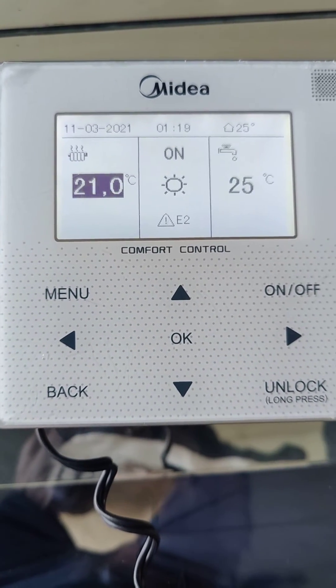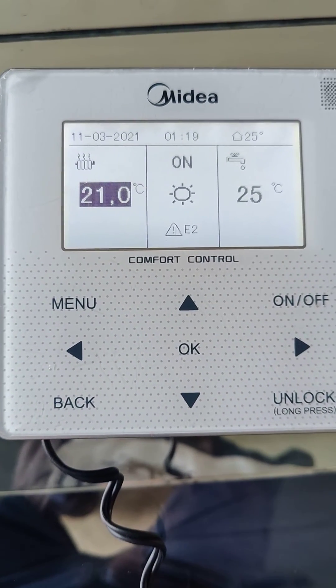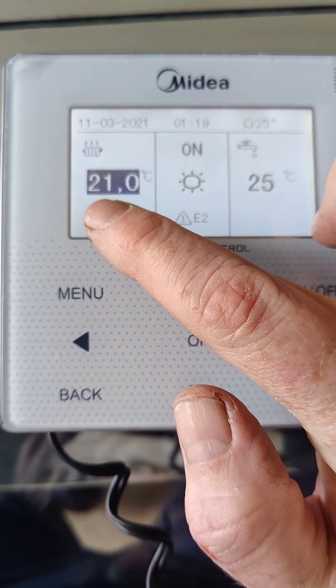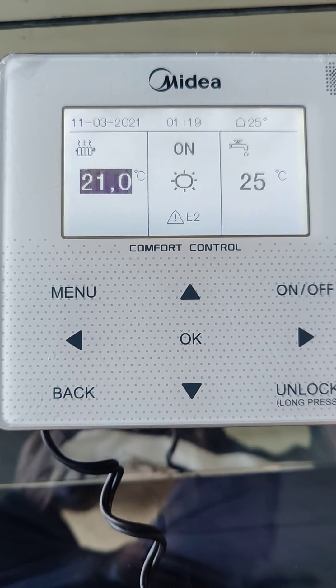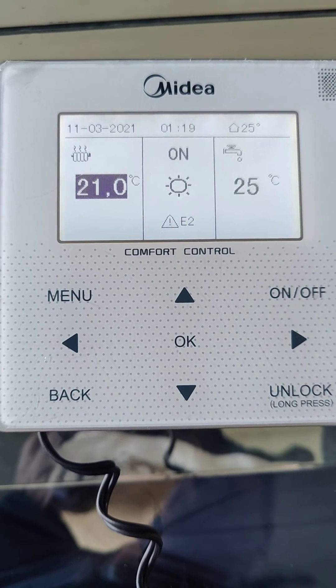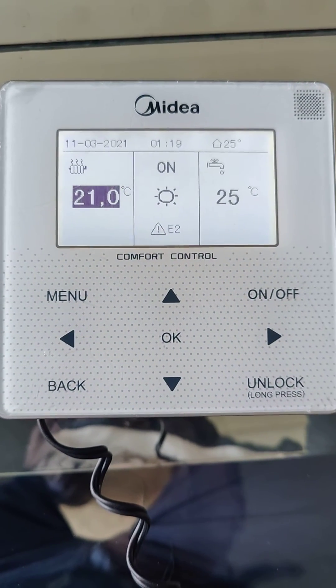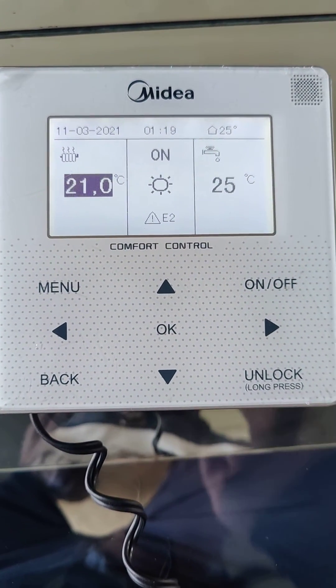What this will do is first use the weather compensation that you set up, but then as it's closing in on the room temperature, it will reduce the water flow temperature to make the machine more efficient.